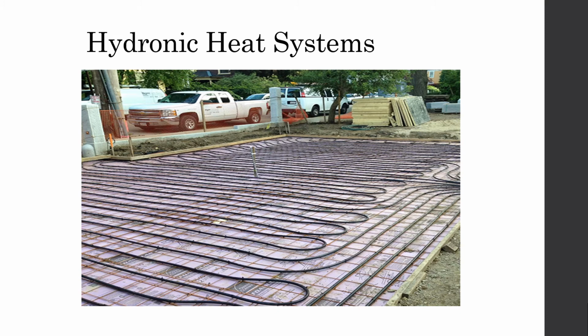The heat is then transferred from the fluid through the concrete to warm the surface of the ramp. In this case, diluted glycol was chosen as the working fluid as it has both a low freezing point and a high heat capacity. Most standard hydronic heat systems reheat the fluid using a boiler after it has exited the heating zone. This, however, is an expensive and energy-intensive stage of the process.